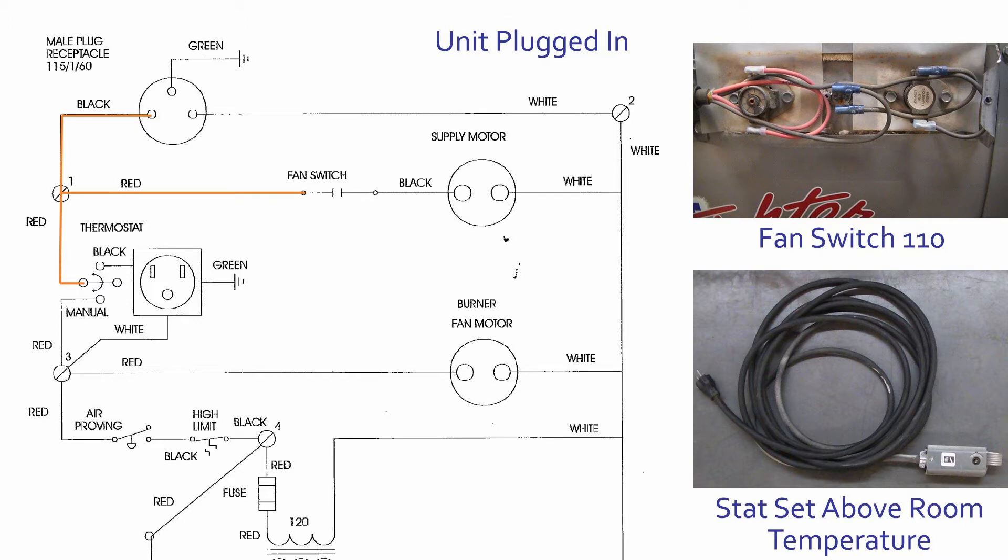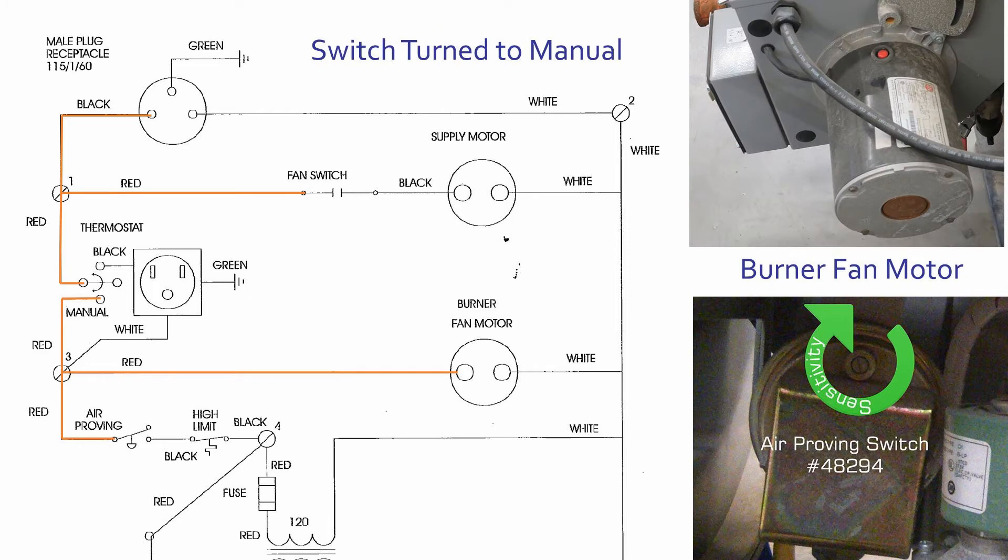If the thermostat setting is set below the actual room temperature, the unit will not turn on. If the thermostat is calling for heat or the three position toggle switch is set to manual, the burner fan motor will then activate.